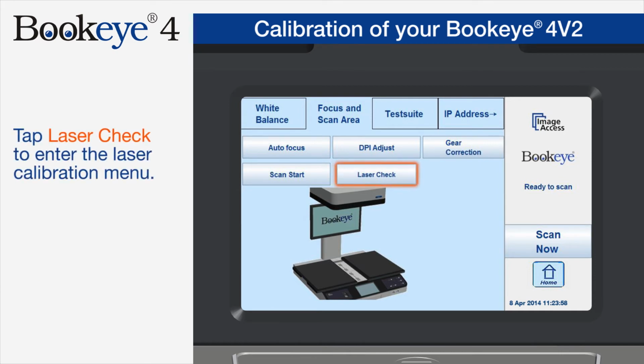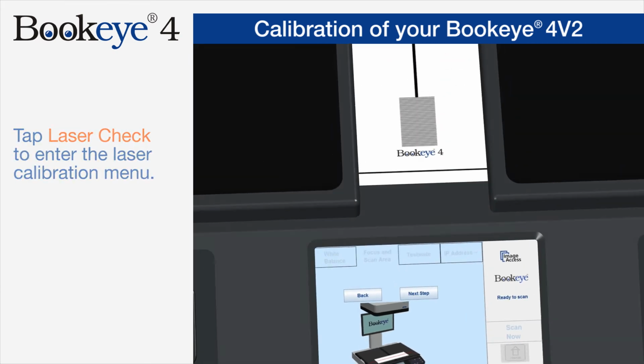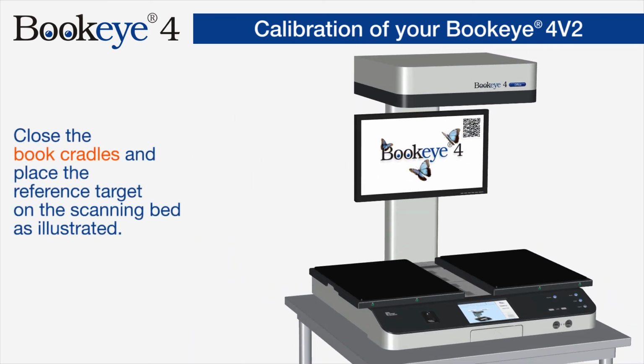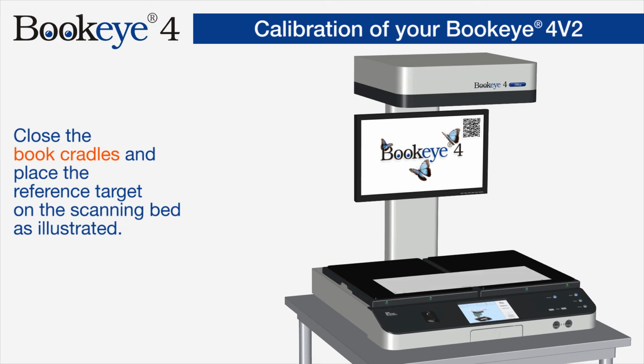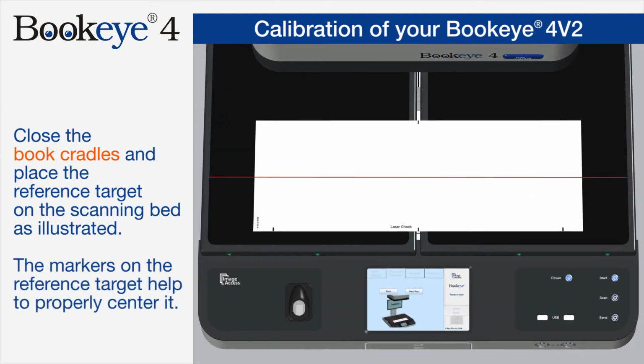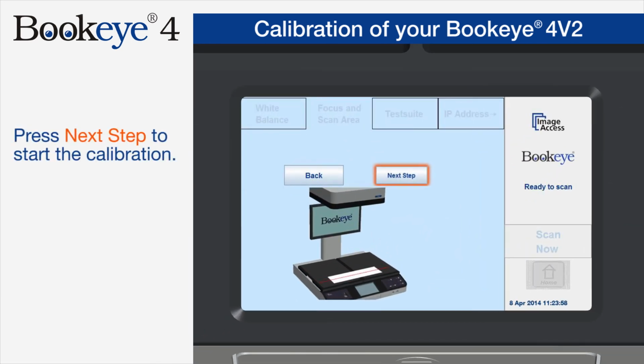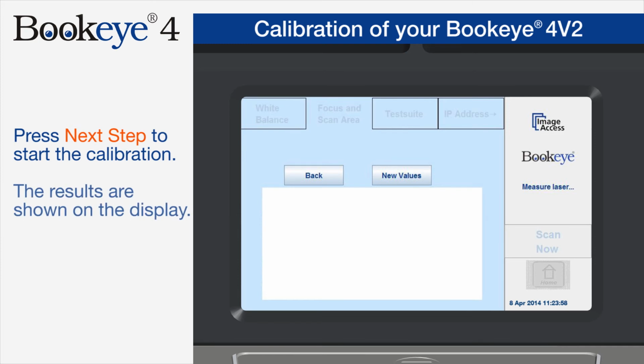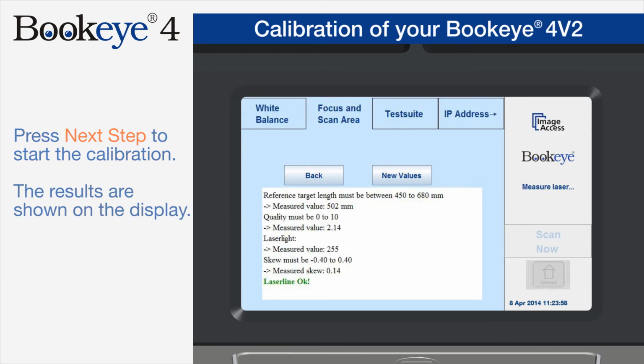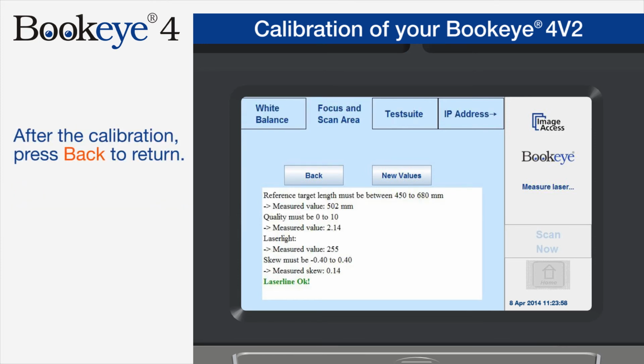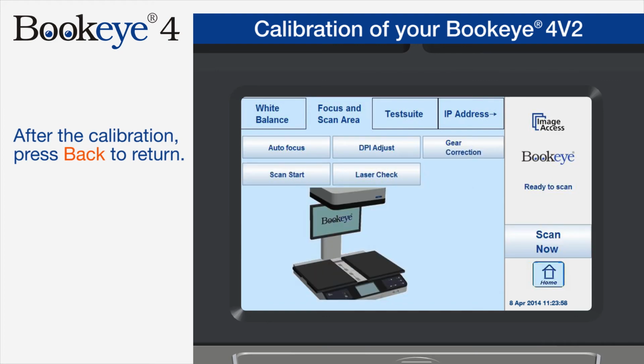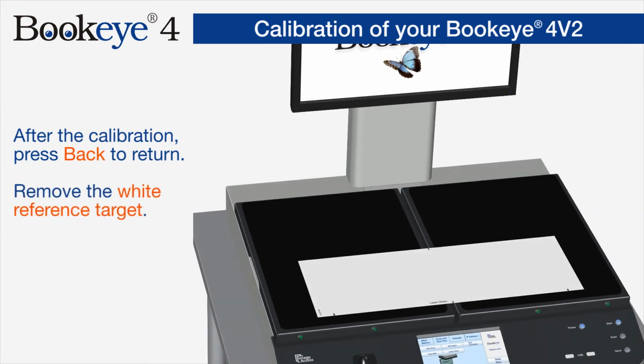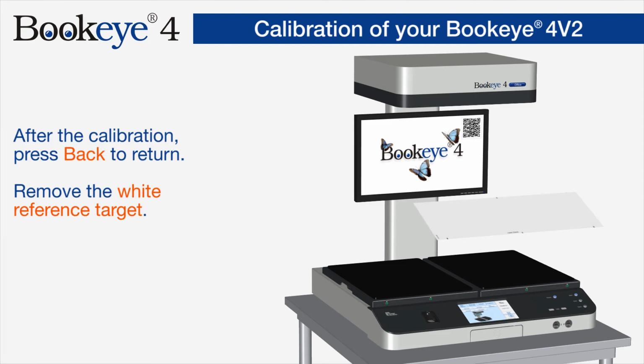Tap the Laser Check button to enter the Laser Calibration menu. Close the book cradle and place the reference target on the scanning bed as illustrated. The markers on the reference target help to properly center it. Press the Next Step button to start the calibration process. The results are immediately shown on the display. After the calibration, press the back button to return. Remove the white reference target and store it in a safe, dark place.